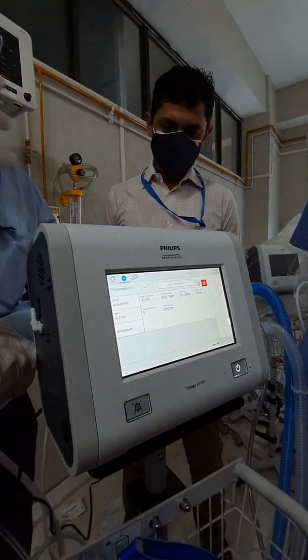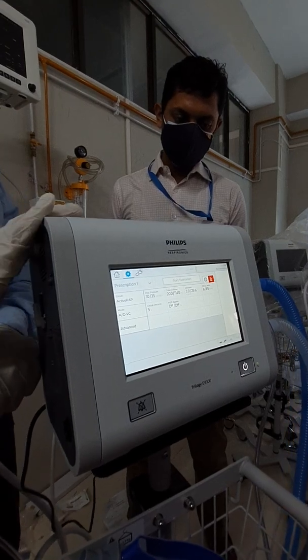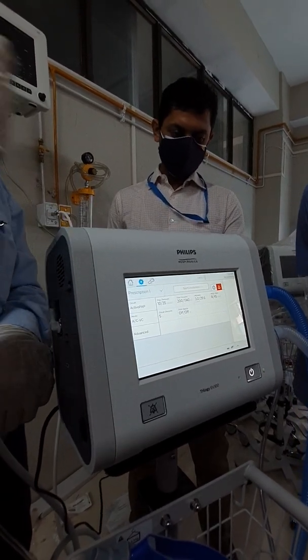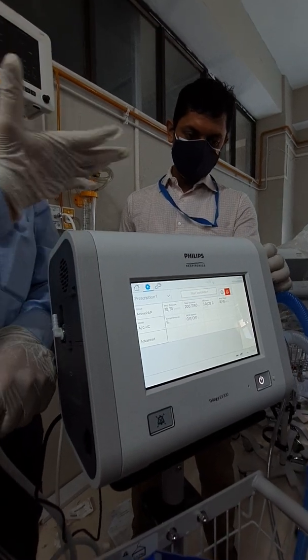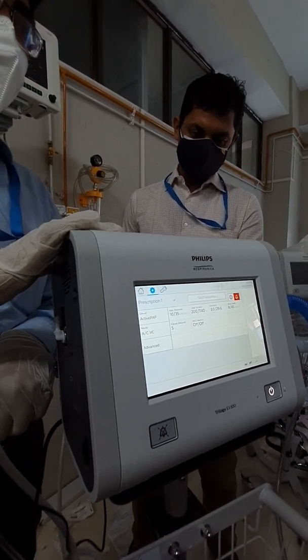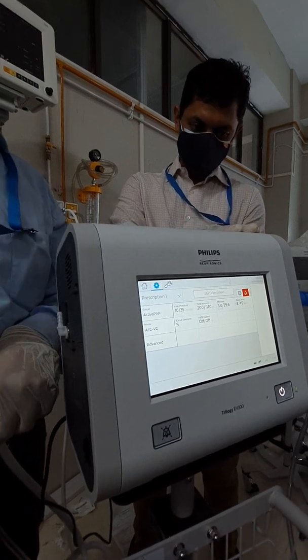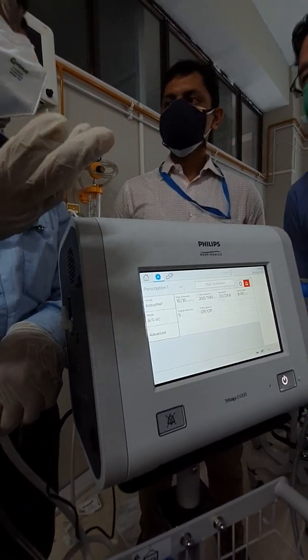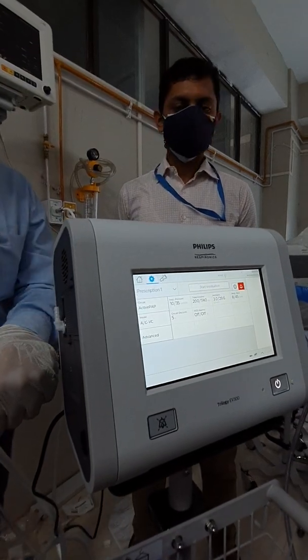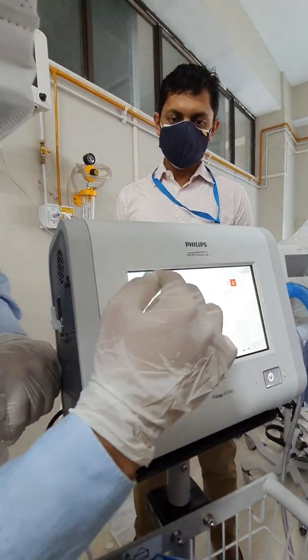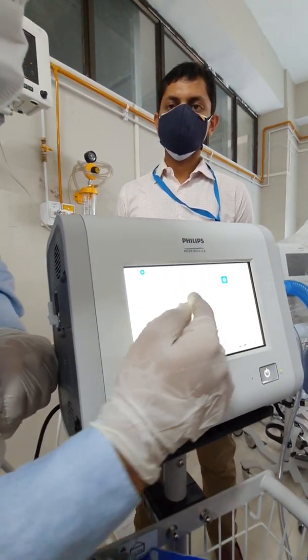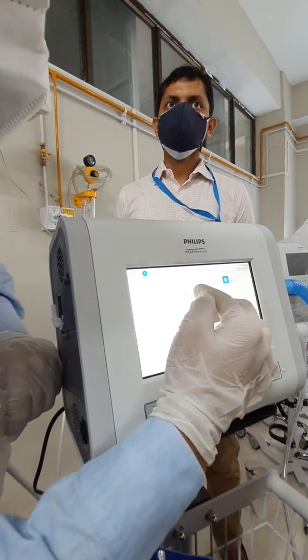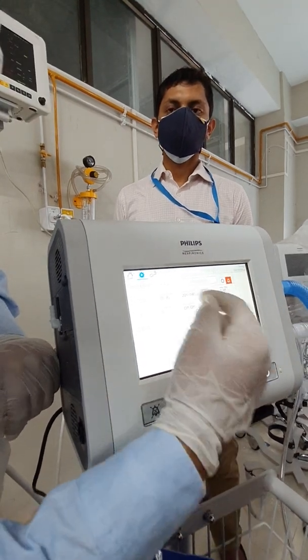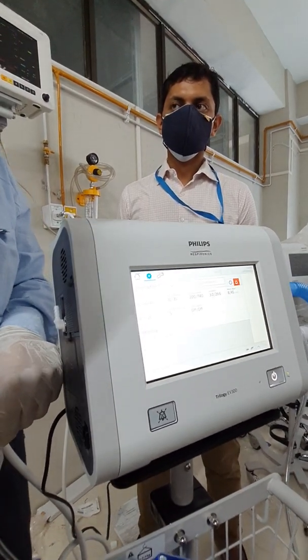Now, suppose a practical case of ARDS. You're trying to do it with volume control. You have set a volume of... I don't know what kind of procedure you follow, but normally it says that for an ARDS patient you should follow the low tidal volume procedure. You should not give too much. ARDS net protocol, yeah, right. So I am talking about ARDS now. So if you are going here, settings, and you have set 380, yeah, we need to change it. Let me just start. 380, then again you see 200 is fine. So that is why I always keep it at 200.